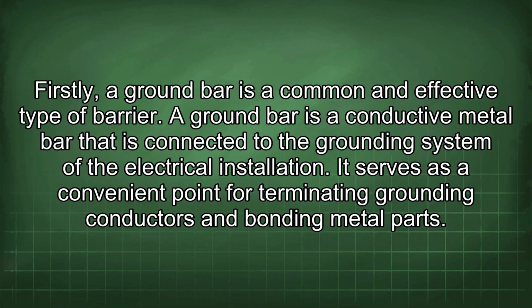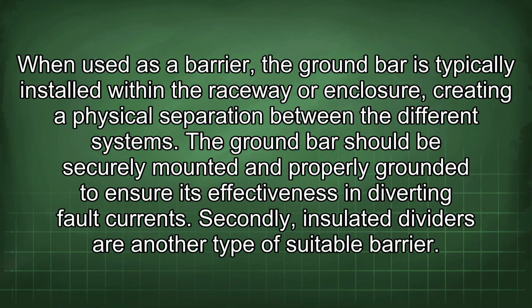Firstly, a ground bar is a common and effective type of barrier. A ground bar is a conductive metal bar that is connected to the grounding system of the electrical installation. It serves as a convenient point for terminating grounding conductors and bonding metal parts. When used as a barrier, the ground bar is typically installed within the raceway or enclosure, creating a physical separation between the different systems. The ground bar should be securely mounted and properly grounded to ensure its effectiveness in diverting fault currents.